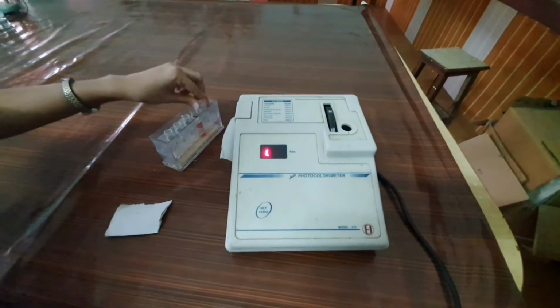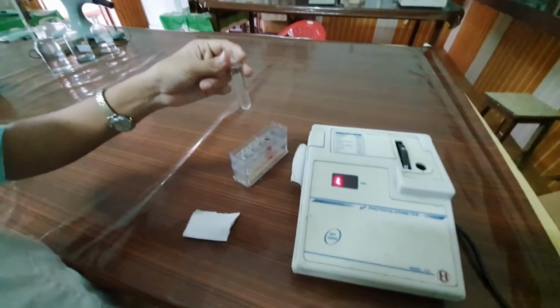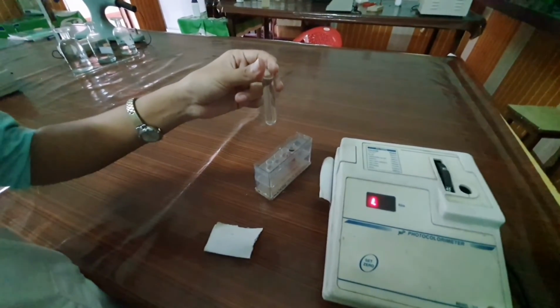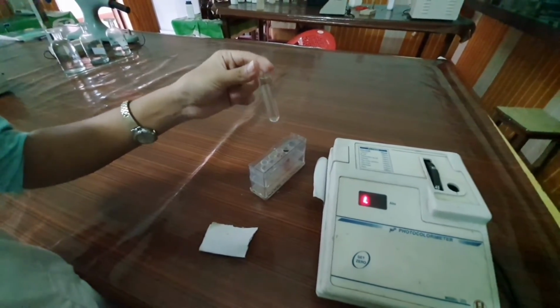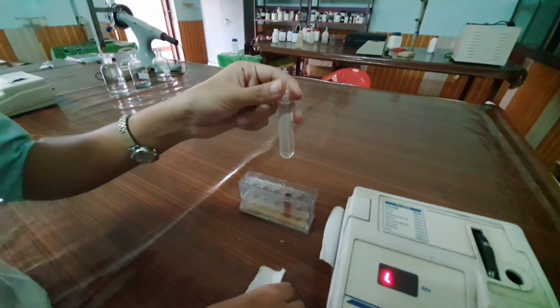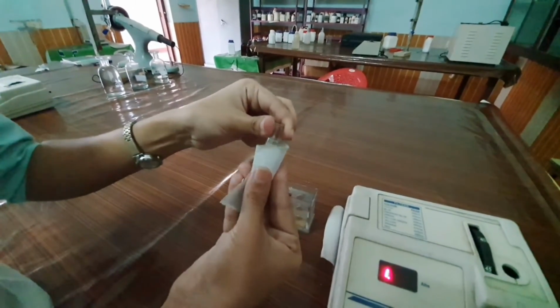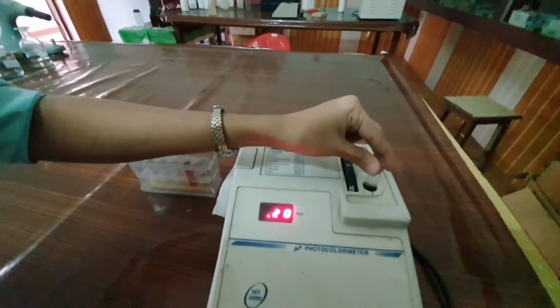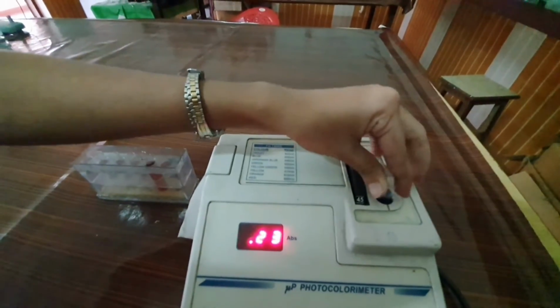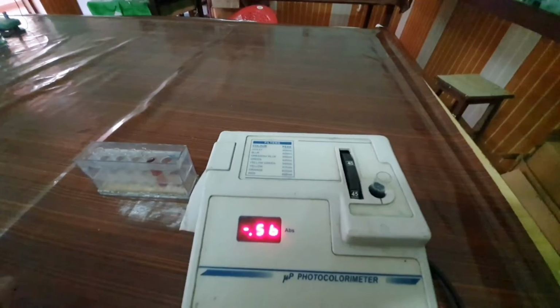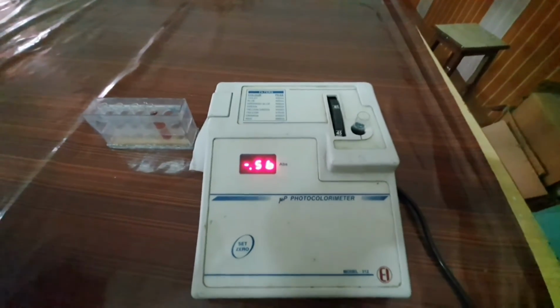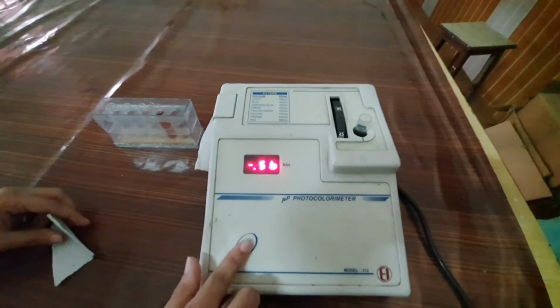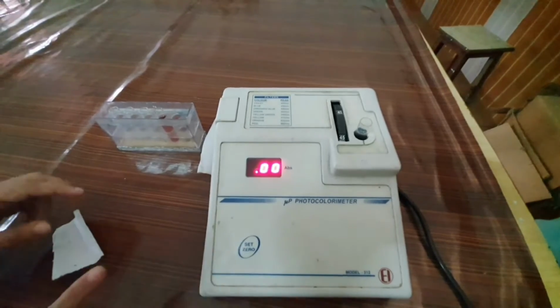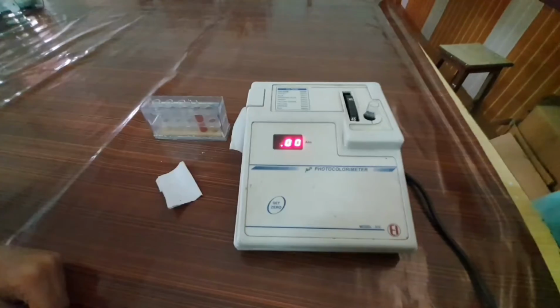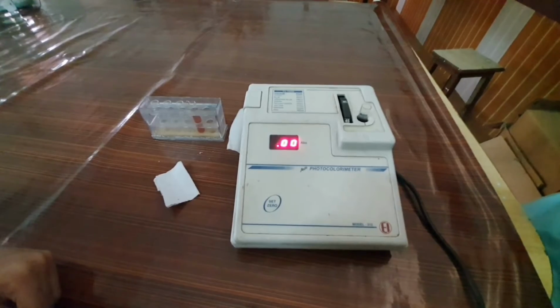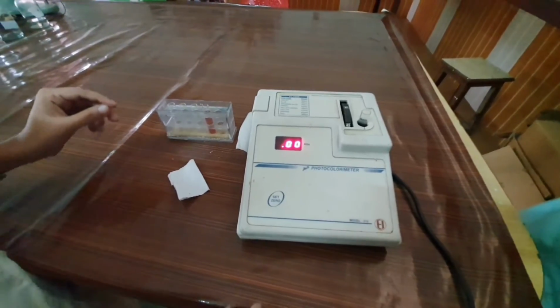Blank. Blank is the reagent used for the reaction. It does not have the analyte which is going to be measured. Clean the cuvette very well. Place it in the cuvette holder. Before starting the experiment, we have to set the optical density at 0. Then we can take the optical density of various solutions.